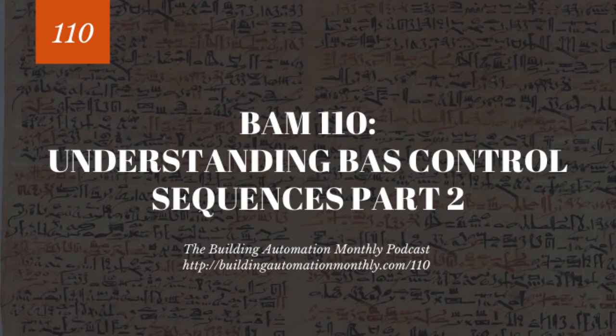Essentially, you have two ways of controlling air volume in the space. That's our primary goal with these units, controlling air volume, because air volume controls temperature in most cases. As we'll see with a VAV reheat unit, that's not exactly true because we have a reheat valve, but it's mostly true, and that's what we're looking to focus in on. So like I said, a VAV is a variable air volume unit.